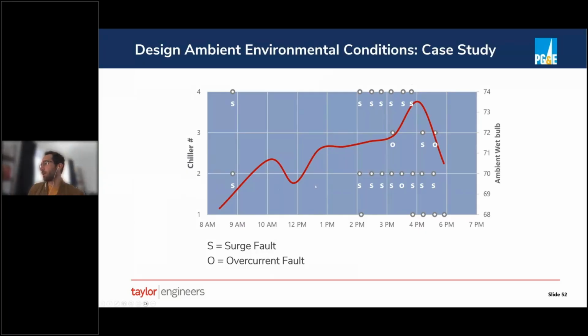We then see by 2 in the afternoon, obviously the ambient wet bulb just kept getting higher and higher, which is what this red line is showing throughout the day. And by 2, they just started having repeated trips on surge conditions across all 4 chillers, as well as overcurrent faults, which is another condition that can occur as a result of surge. And so we basically had operators playing whack-a-mole to keep the chillers online and prevent this colocation data center from going offline. So this is here to demonstrate what can go wrong if you don't consider or choose the right design ambient conditions for your data center.